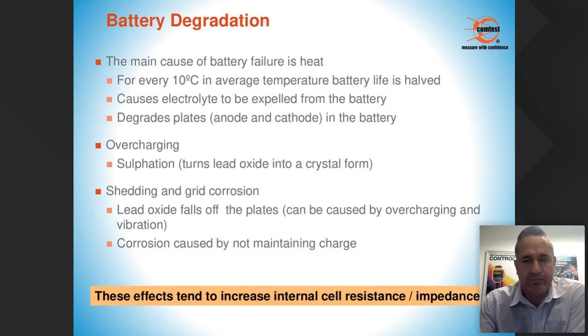Why do maintenance-free batteries fail? Thermal runaway, they get too hot. Loose terminal and inter-cell connections. Overcharge and over-discharge. Ripple will relate to your charging system. If you don't have a pure DC system charging your batteries, that could also cause them to fail. And then the age of the batteries has a big effect as well on the longevity and the performance. What happens when one battery in a string fails?